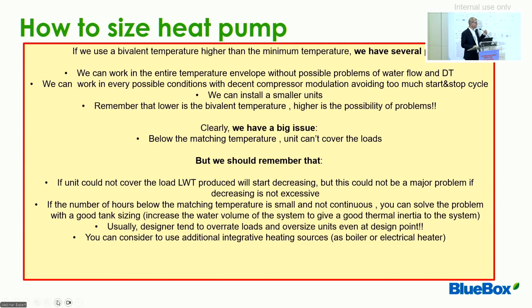Usually, a lot of designers tend to overrate the loads and oversize the units even at design point. So the loads calculation is generous and the unit selection is even more generous. Or in some cases, it may be more efficient to consider integrative heating sources below a certain temperature.